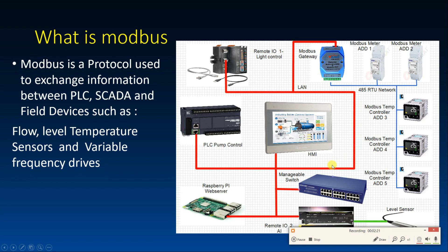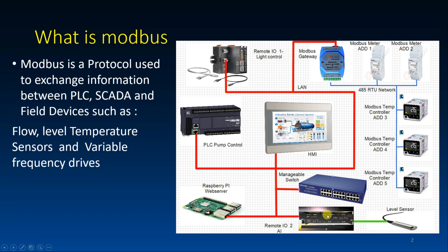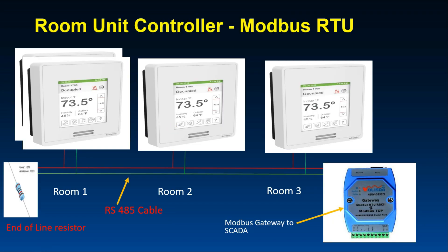This is a setup of a Modbus network. Here we have the LAN and the Modbus RTU, along with remote data acquisition modules for level monitoring. For example, in a hotel with several air conditioners, from a main computer we can control each one by assigning addresses — room 1 gets address 1, room 2 gets address 2, and so on. The two communication lines, wires A and B, connect all devices in parallel and then run to a Modbus gateway.